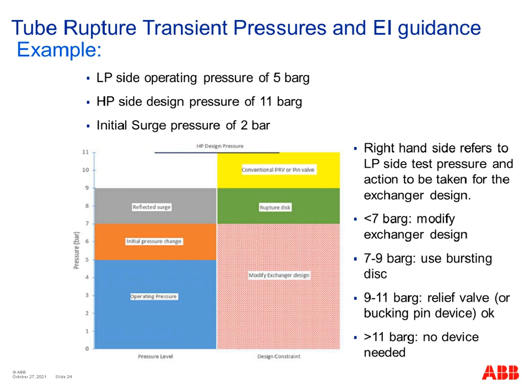And then with the reflected surge, you get another 2 bar, and that takes you up to 9 bar gauge overall. So on the right-hand side, you're looking at the design constraint for the LP side based on what the test pressure actually is. So if your test pressure of the LP side is less than 7 bar gauge, you're in that bad place I talked about in the previous slide.